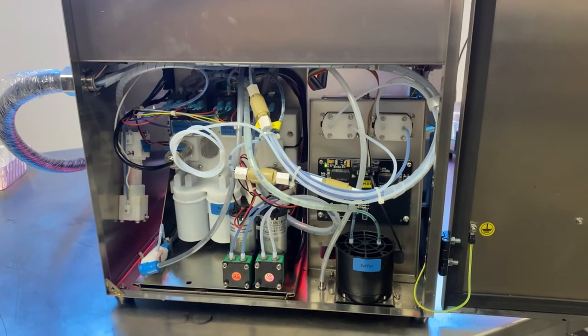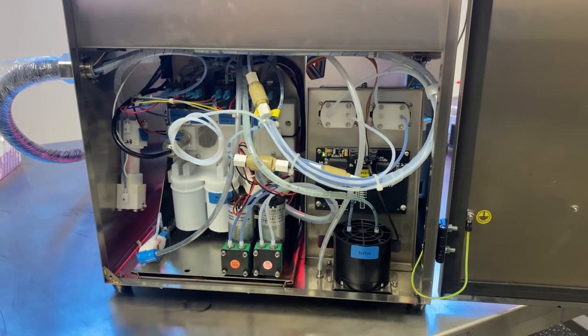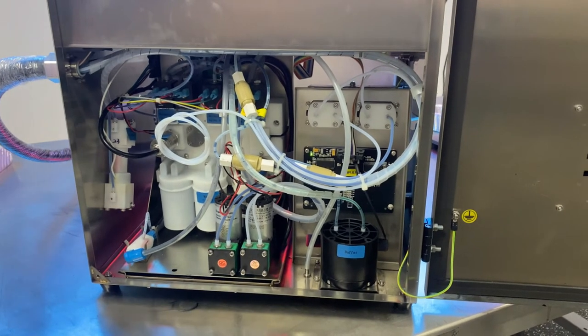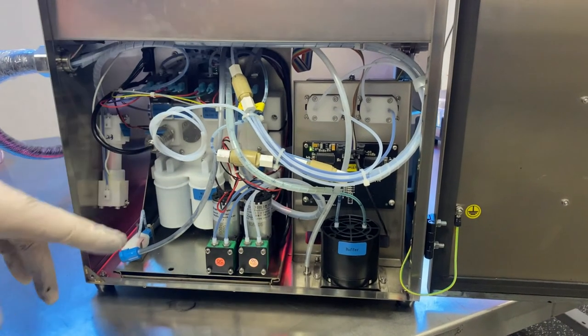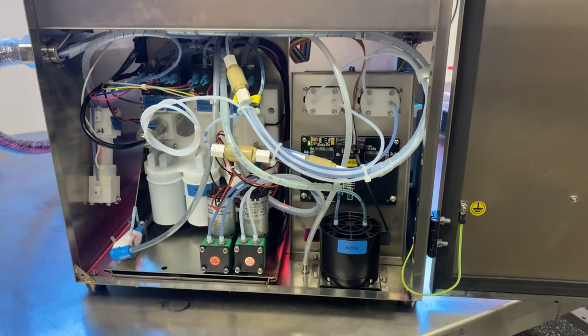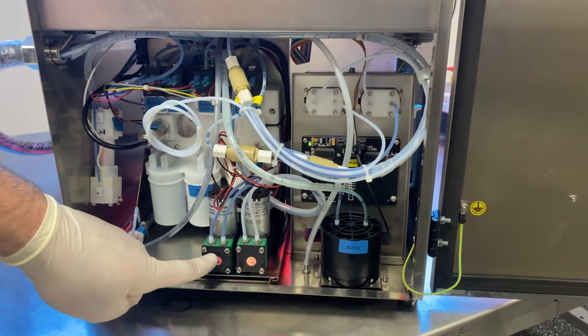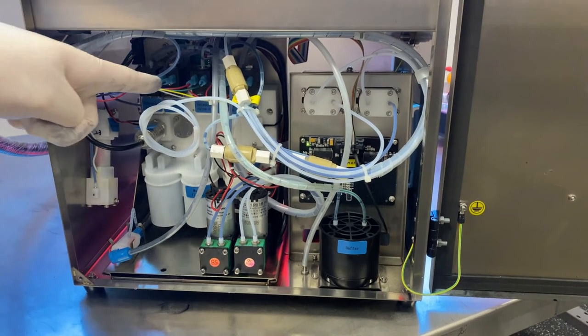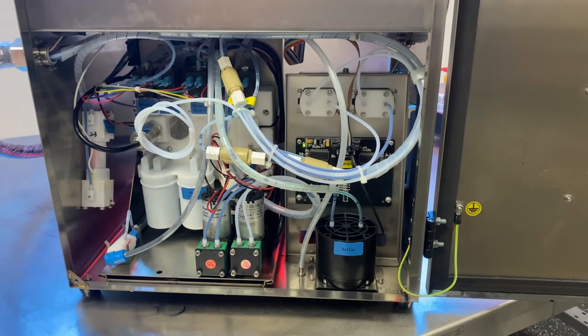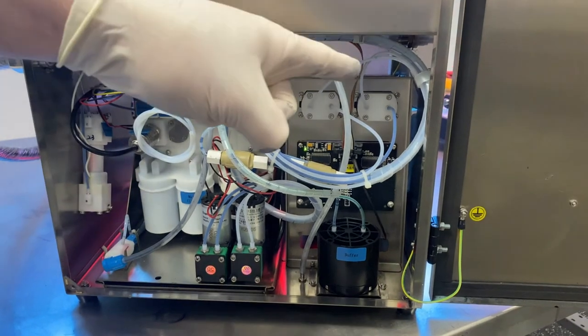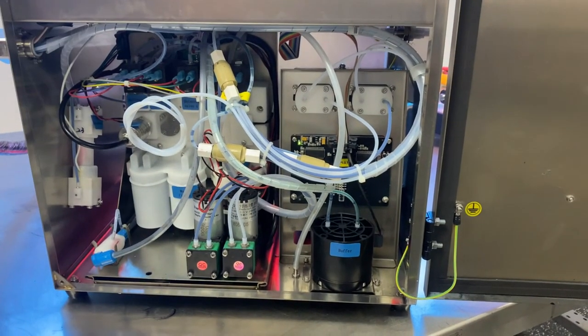And I'll also show you another trick. We'll basically use the same visual indicators. We can do this exact same process with system diagnostic as well. So we could activate our ink replenishment pump, we could open valve 6, just using that system diagnostic. We would also achieve the same result of getting fluid from the cartridge to the mix tank.